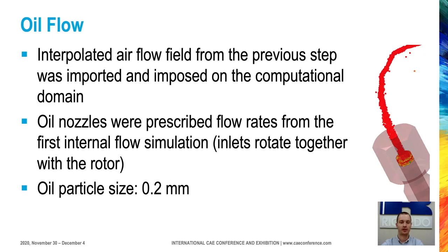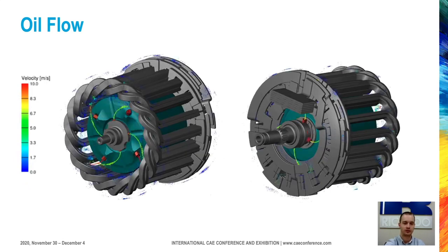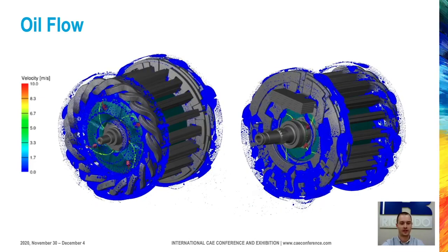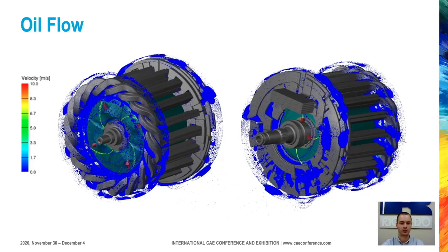Now we come to the last third CFD simulation of oil. As discussed, we used the air flow field from the previous simulation and also the flow rates for the nozzles from the first simulation. The inlets were placed right at the nozzle, so we didn't have to solve for the internal flow anymore, which helped reduce the total runtime. The oil particle size was 0.2 millimeters as discussed before. We have a view of each side of the motor, and as you can see, the oil starts accumulating on the windings and at the very end starts dripping from the windings.